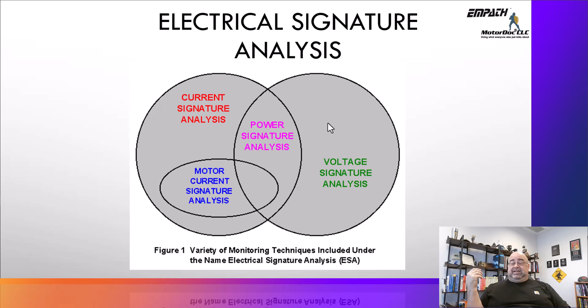In a wind turbine, I do the transformer, generator, coupling, 3 stages of gearbox, a planetary gear set, the 2 main bearings, and even the condition of the blades. Through a reading that takes 1 minute with the Empath and 2 minutes with the Empower. Okay, so that's part of it.